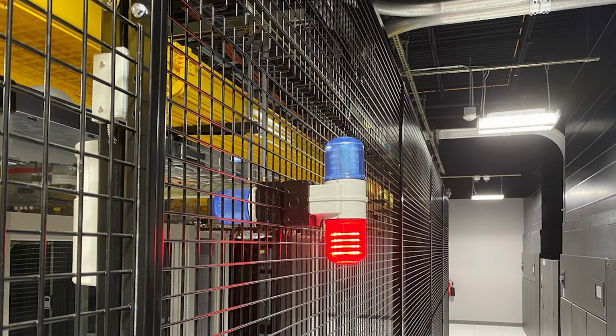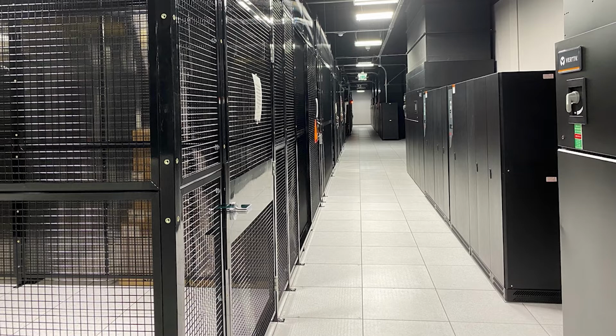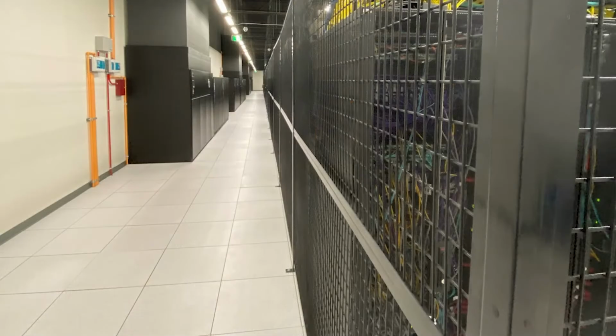Power densities of up to 100 kilowatts per cabinet can be achieved utilizing a water-cooled backdoor configuration. The data halls are configured with CRAC units along the outer edges of the room. The CRAC units are powered by a primary and secondary feed, which are both backed up by generators. Power distribution is also set up along the outside walls of the primary A side, delivered from the east side of the room, and the secondary B side, delivered from the west side of the room. This provides physical separation of the A side and B side power whips all the way to your cabinet.